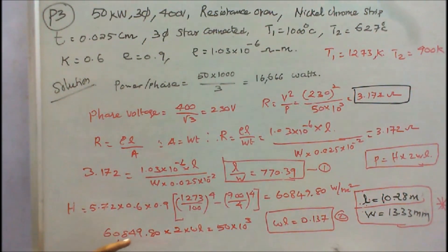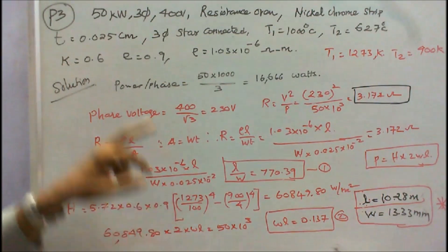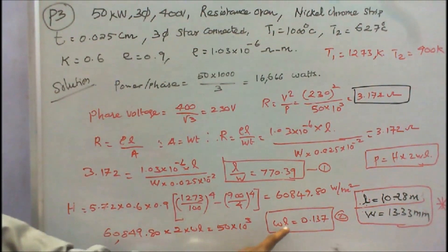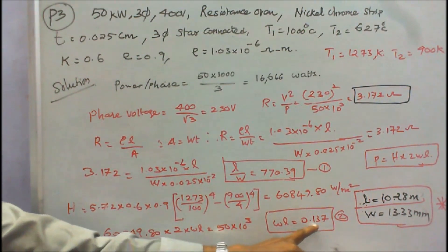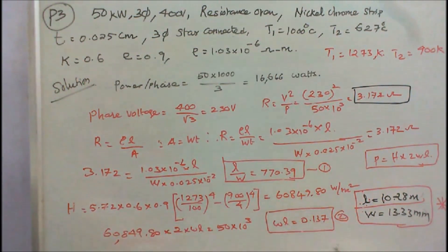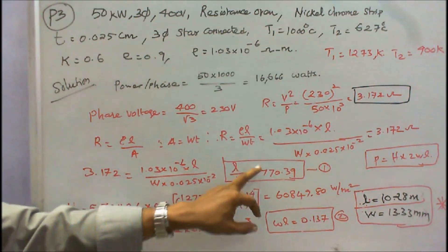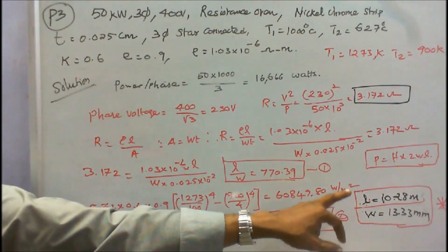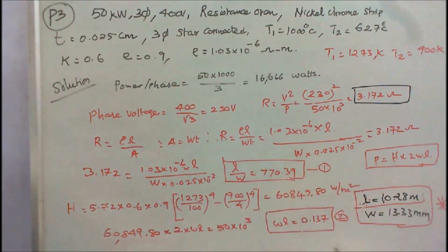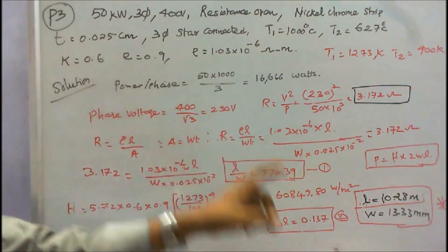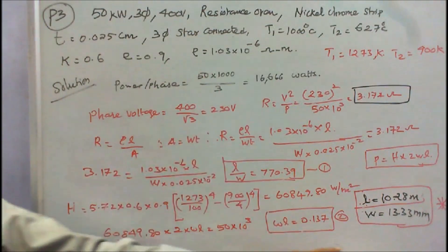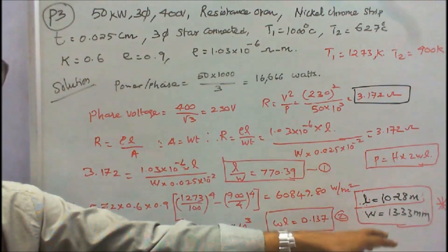Input power equals H times surface area, where surface area of the strip equals 2 × W × L. Substituting gives W × L equals 0.137. This is equation 2. Solving equations 1 and 2 simultaneously gives length L equals 10.28 meters and width of the strip equals 13.33 mm.